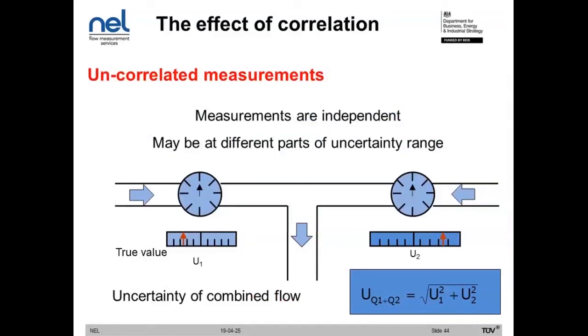So we have a flow meter at location 1 and a flow meter at location 2. Each of those has a measured value, a true value, an uncertainty, an error, all these different components. If these devices and their uncertainties are uncorrelated, then it's fine to combine the measurements of them using the root sum squared method. So the calculation for that is shown in the bottom right-hand side. The overall uncertainty for the combined flow rate determination is based on the uncertainty of flow meter 1 squared plus the uncertainty of flow meter 2 squared, and find the square root of that. This is fine because we expect the uncertainties and the errors of each of these devices to be uncorrelated and somewhat random. So they combine in an acceptable way.